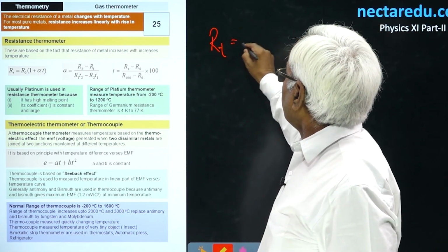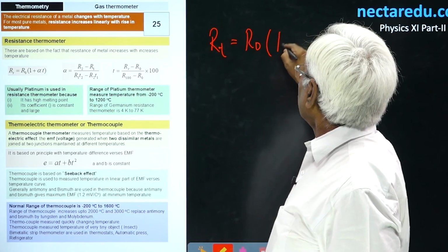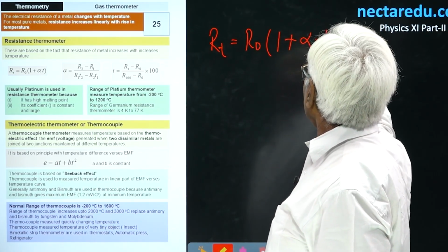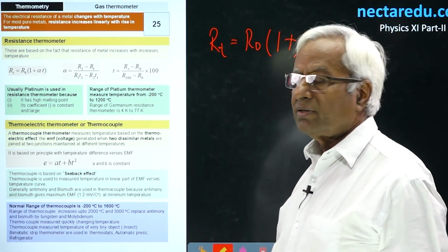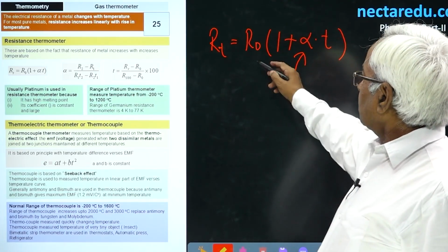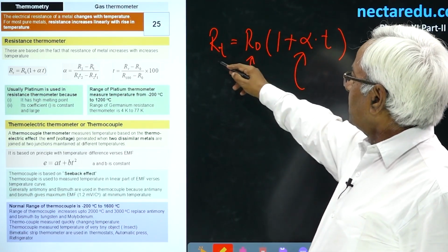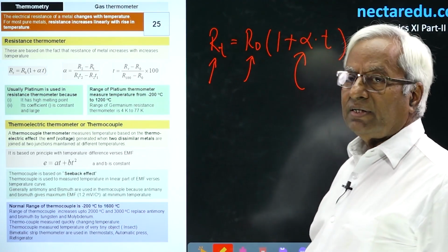So, the platinum resistance thermometer is mostly preferred. The relation that we follow is R = R0(1 + alpha T). Alpha is known as the temperature coefficient of resistance, R0 is the resistance at 0 degrees, and R is the resistance at T degrees.